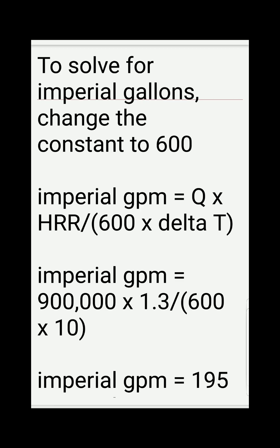Substituting the known and calculated values: imperial gallons per minute equals 900,000 BTU/hr times 1.3, divided by (600 times 10 Delta T). Using our calculators, we arrive at the answer of 195 imperial gallons per minute.